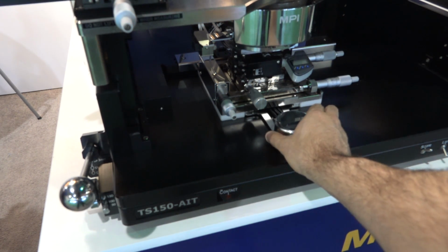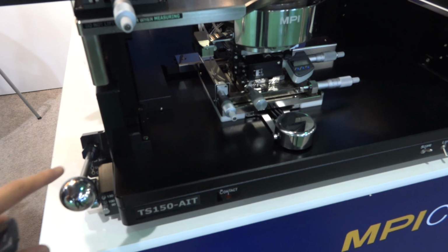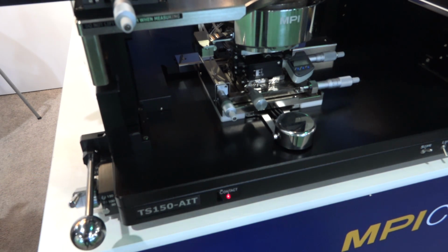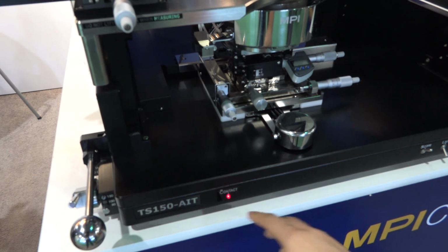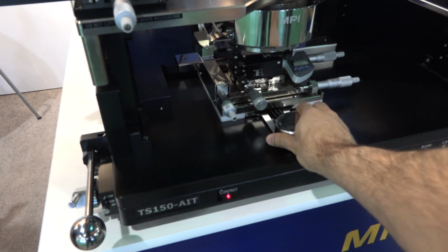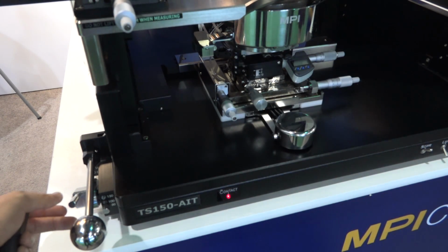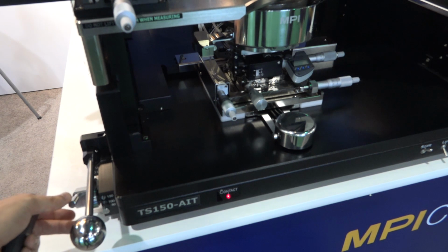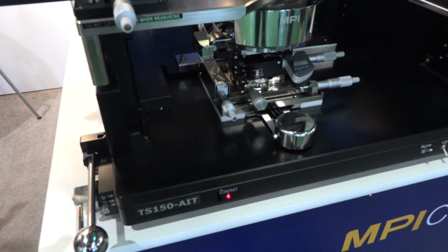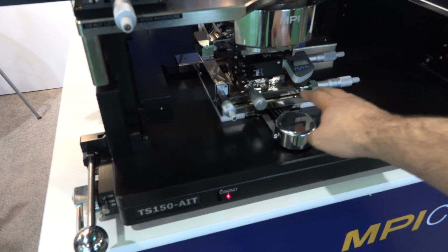As I showed you, you can have free movement here. Now as soon as I land the probes by just touching it, so now we have contact, the contact line is on, so you know that this is locked, you can no longer move it, but you can still move the probes up and down by very precise movements, 50, 100, or 150 micron distances, and this allows you to get extremely high repeatability landing on the probes while still allowing you very fine movements.